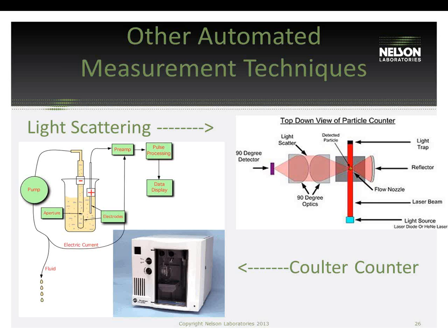The Coulter counter has also been used for particulate measurement, not as frequently as it used to be. More used for biological material now than particulate measurement, but using an electrostatic potential, it does have the ability to at least count, if not somewhat size, particles.